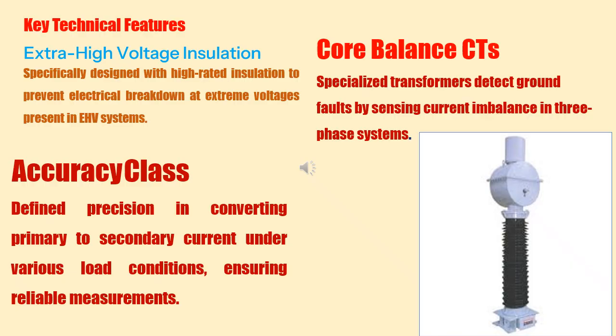Key technical features of EHV CT. First, extra high voltage insulation. Second, core balance CTs. Third, accuracy class. Extra high voltage insulation: especially designed with high rated insulation, prevents electrical breakdown at extreme voltages present in EHV system. In core balance CTs, specialized transformers detect ground faults by sensing current imbalance in three-phase system. In accuracy class, defined precision in converting primary to secondary current under various load conditions, ensuring reliable measurement.